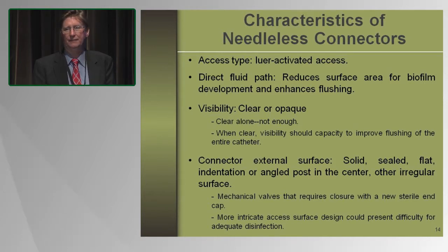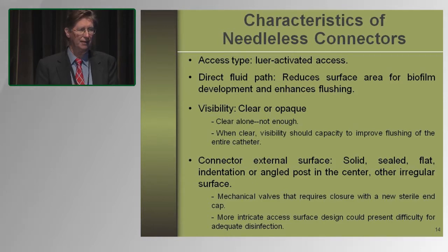Is it solid? Is it sealed? Is it flat? Or is it indented, angled post, or other irregular surface? Some of the mechanical valves have required end caps to keep them sterile, and getting compliance with putting those caps on is very difficult. And we know that the more intricate the access surface, the more difficulty it is for clinicians to adequately disinfect them.